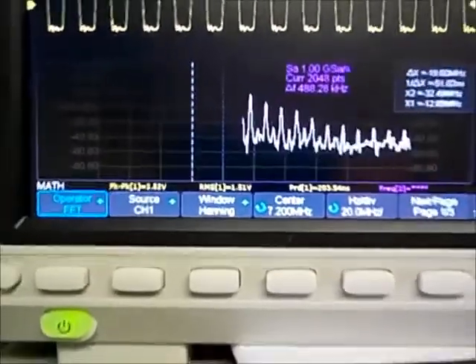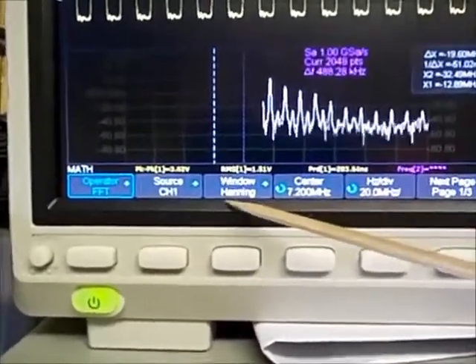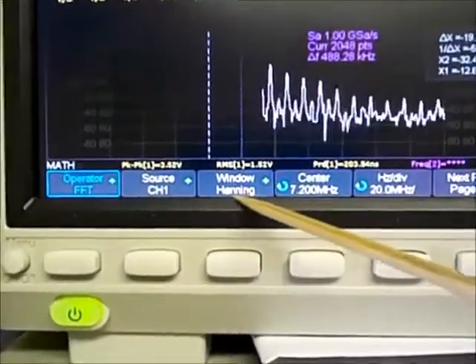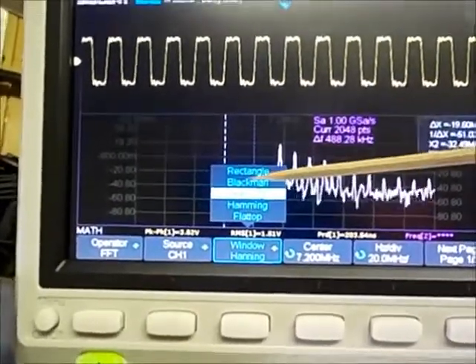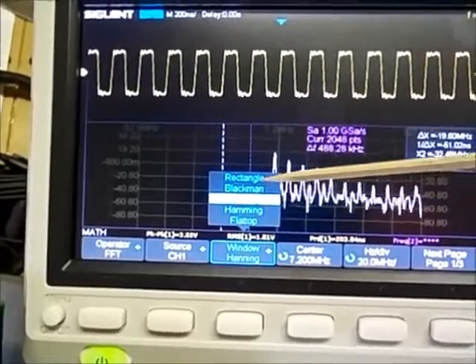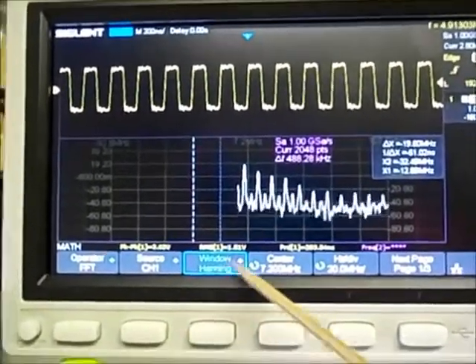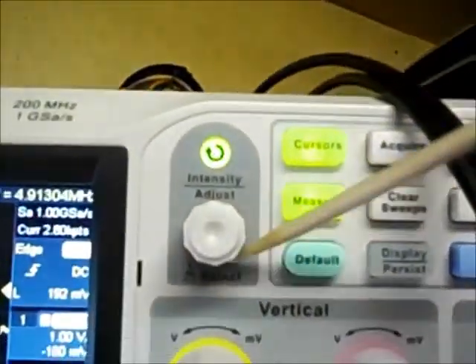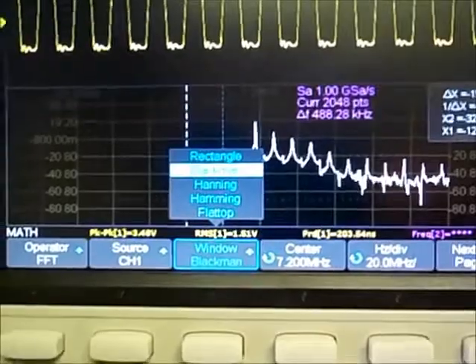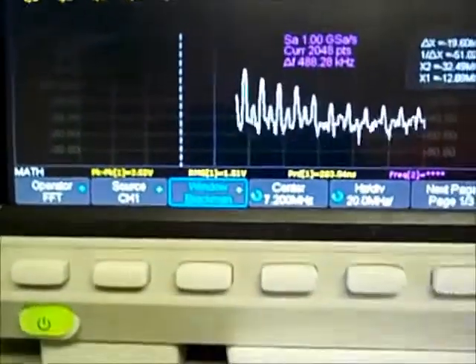The next thing is the window. Depending on what resolution you want, the window takes off extraneous frequencies — it puts an envelope across the signal. Hanning is the default. If you use Blackman, you get better amplitude resolution. Hamming and rectangular give you better frequency resolution. I usually leave it at Hanning. You select the window by turning the universal cursor adjustment knob and then pushing the button to select it.